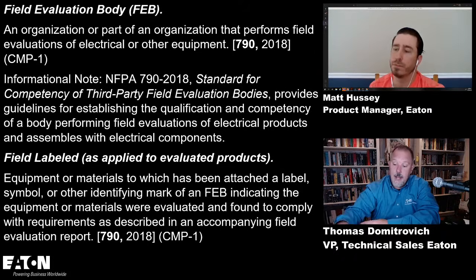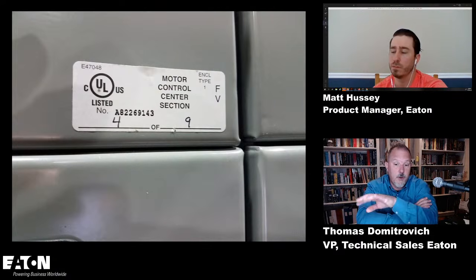You'll have that label that says 1 of 4 or 1 of 9, 2 of 9, 3 of 9, 4 of 9, etc. And those two sections will still say 1 of 2 and 2 of 2, but your documentation or somebody would have to document that it is now part of this whole motor control center. Yeah, you want to be able to trace back to its original equipment designs and whatnot. Yep. Okay.